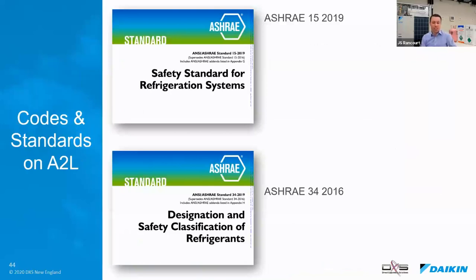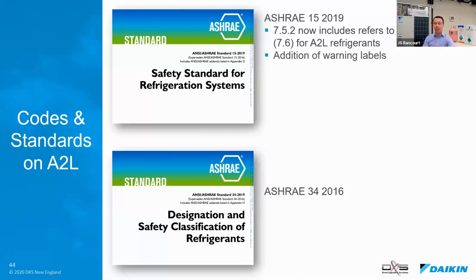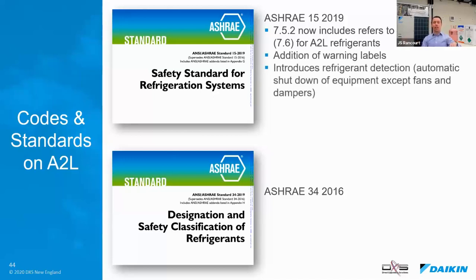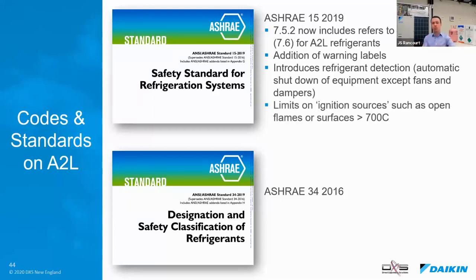Let's get into codes and standards. So ASHRAE 15, which we talked about, is now on the 2019 edition, and they have now created a brand new 7.6 section specific to A2L refrigerants. ASHRAE 15, 2019, starts to introduce things like adding warning labels. But the big one is the introduction of refrigerant detection to allow A2L refrigerants in buildings with automatic shutdown of equipment, except for fans, if ever they see a certain amount of refrigerant concentration. It also limits ignition sources in the ductwork or in the spaces.